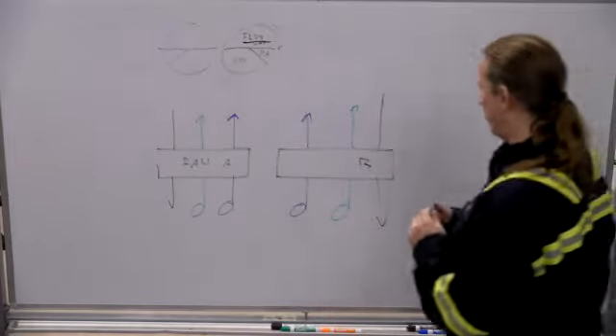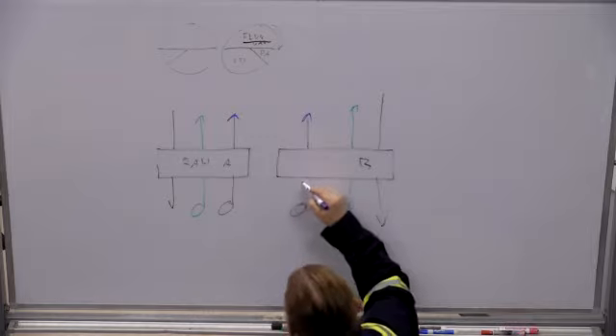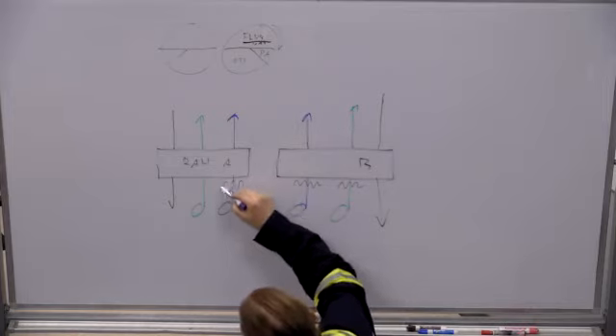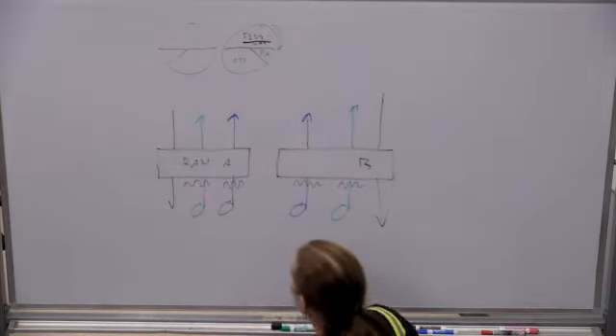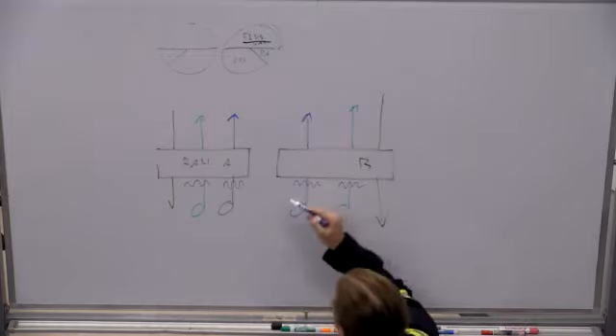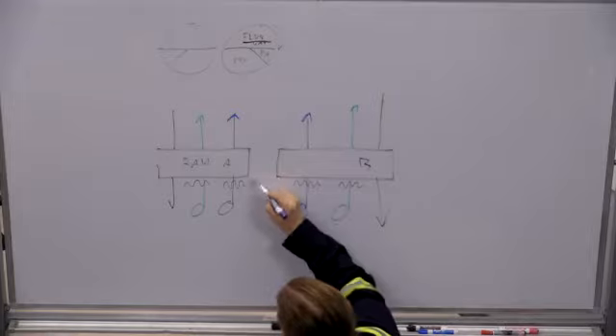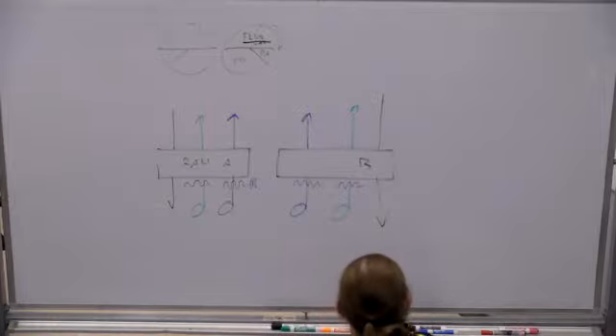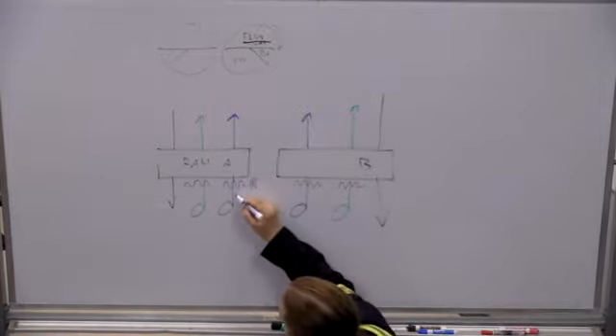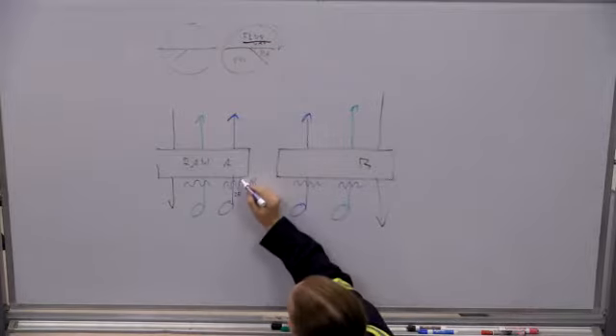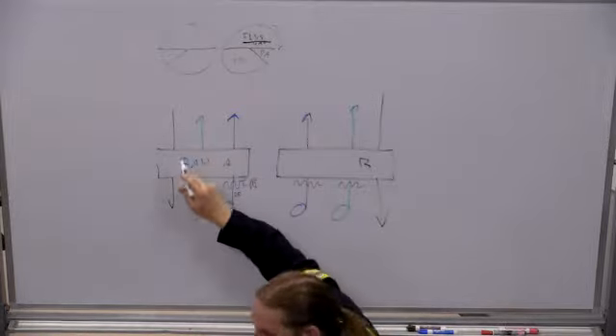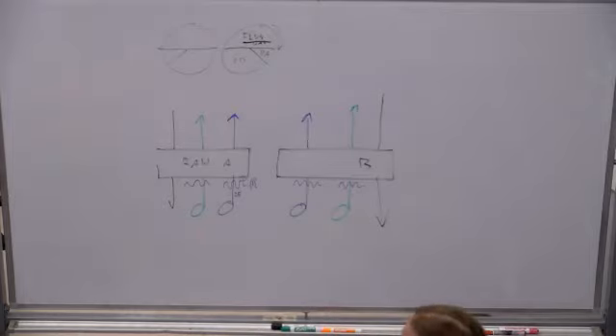So how do we keep from cooling down the flue gas too much? Steam coils. So on the cold end of both the FD and the PA, we've got steam coils that take aux steam and run it inside tubes. And then the gas goes around the tubes and it heats it up. So in the winter, when you might have 25 degree air going in, then you can still have 70 degree air going into your rotary air heaters so that the flue gas doesn't get too cold.